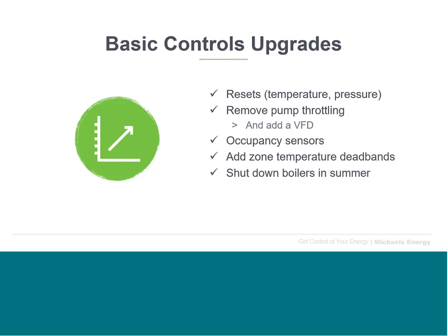equipment is running. Adding some zone temperature dead bands can keep spaces from fighting with each other, and can remove some of the user controllability. One thing that we see very often is a thermostat being set in the morning by somebody walking in and turning it all the way into cooling mode, and then later in the afternoon somebody turns it into heating mode, and it's a perpetual fight. So that can have some substantial energy impacts.